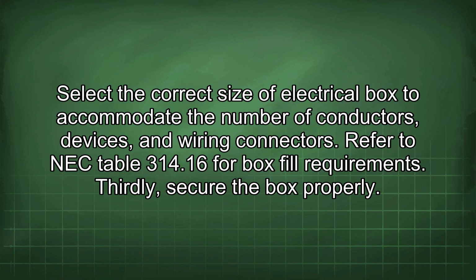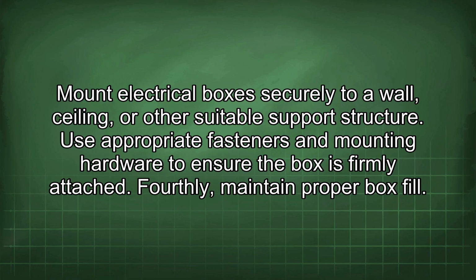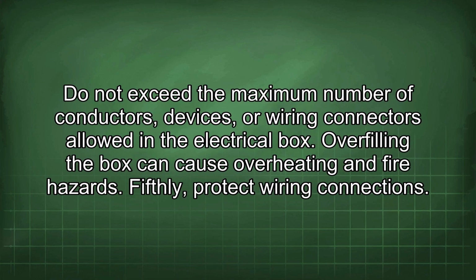Thirdly, secure the box properly. Mount electrical boxes securely to a wall, ceiling, or other suitable support structure. Use appropriate fasteners and mounting hardware to ensure the box is firmly attached. Fourthly, maintain proper box fill. Do not exceed the maximum number of conductors, devices, or wiring connectors allowed in the electrical box. Overfilling the box can cause overheating and fire hazards.